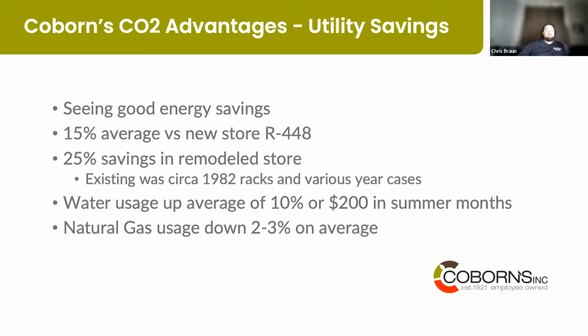Yeah, and then one of the other advantages we're seeing is we were always told that you should see anywhere from a 5 to 10% energy savings with CO2 versus HFC. And a lot of that is due to heat reclaim savings. Some of it's due to efficiency in the refrigerant and stuff like that. We're actually seeing better than that. The 2 new ground up stores that we have are comparable to our prior ground up store in layout, BTU loads and stuff like that. And we're seeing an average of 15% utility savings per square foot, based on our 448, 449 store to CO2.